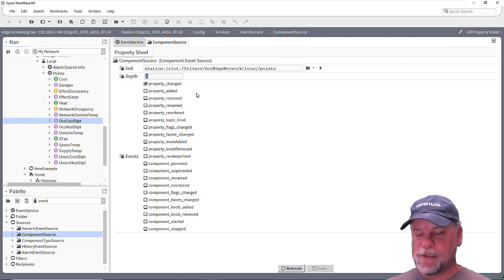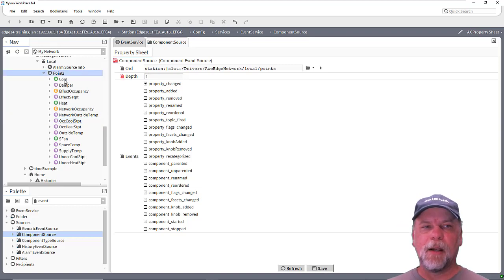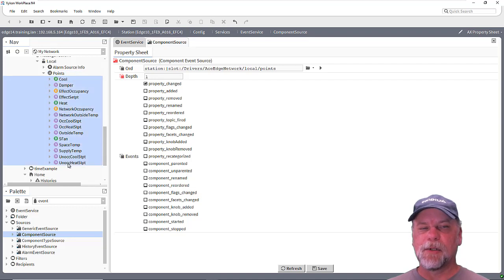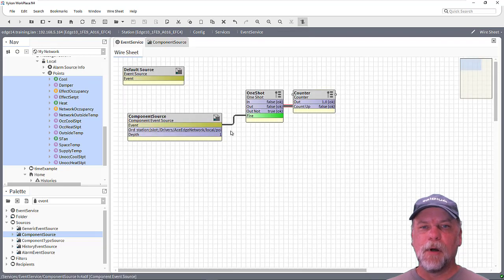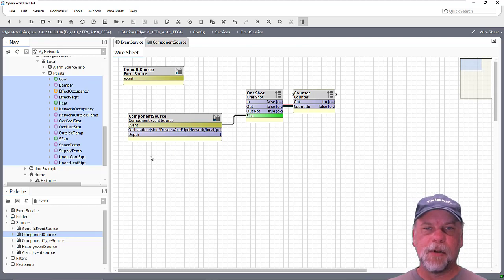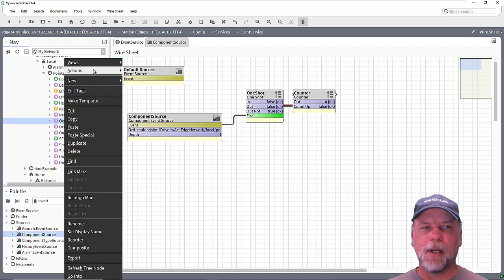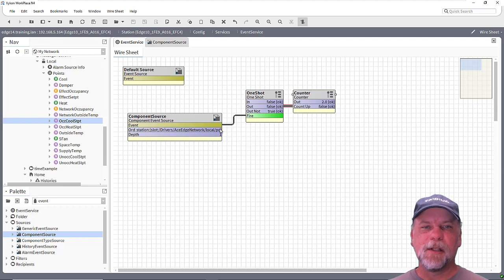So if I set this to one, then what that means is monitor the points container, subscribe to that, and then also one level deep, subscribe to all those components as well. So in this case, it'll subscribe to all the control points under the points container and the points container itself. So then we'll start to see the counter will actually start incrementing — possibly the space temperature changing, or the set point, or some other value changing. If I go over here and invoke an action like set on the set point again, you'll see that the event fires, which fires the action and the counter increments.